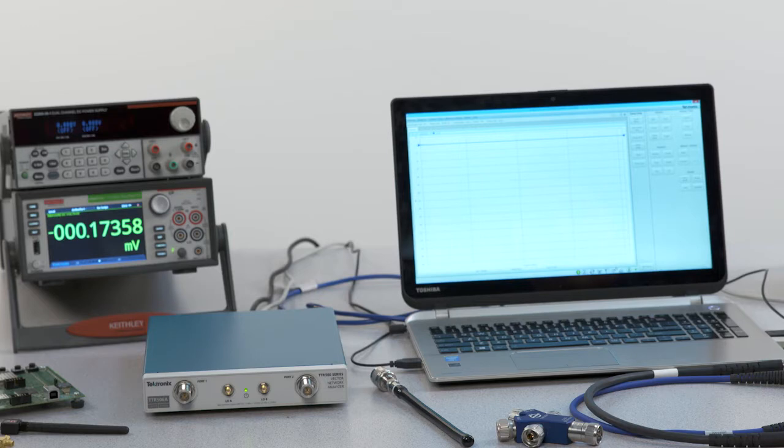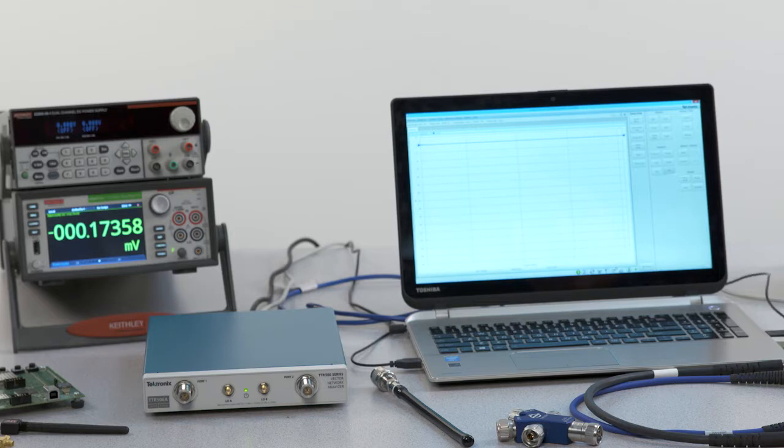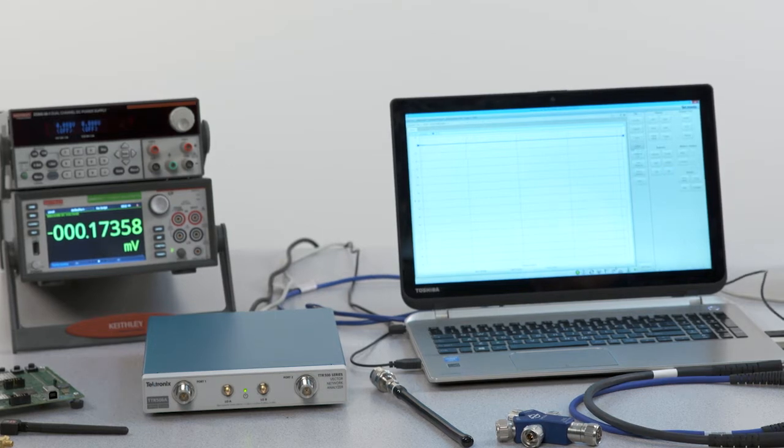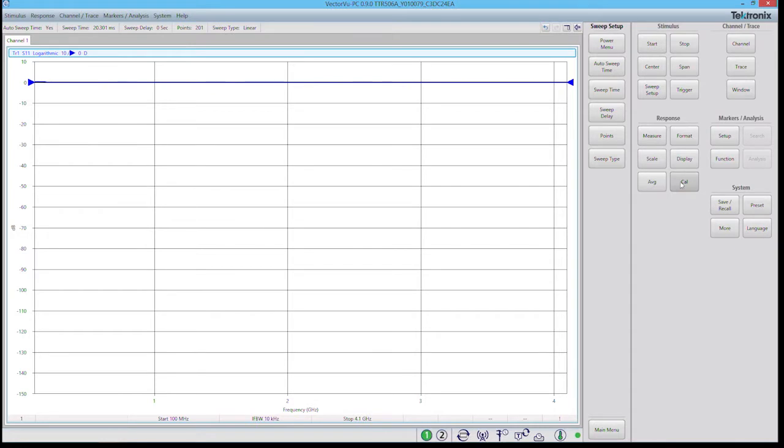Now that we have our sweep start and stop frequency ranges set and our number of points, we can go ahead and begin our calibration procedure. To do that we go under the response menu and click cal.